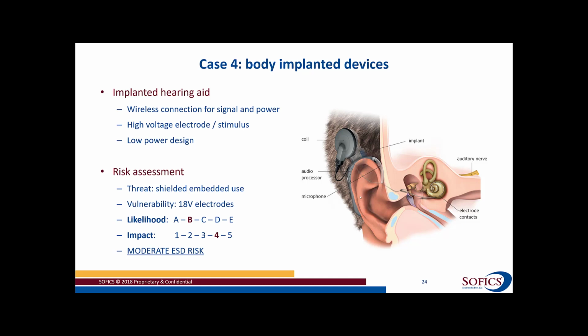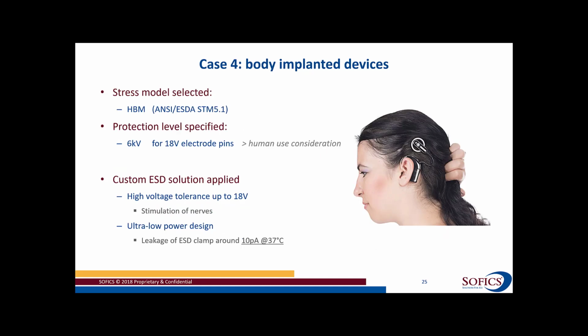What's the likelihood of something to happen? It's in the second column, B, and the impact is going to be higher, because if something happens, this is a body implanted device, so we cannot just ignore that. This leads to a moderate ESD risk. So what was selected in this particular case? Well, in the end, the human body model was used. However, it was an increased performance requirement of 6000 volts, not the standard 2000 volts or 1 kV, but 6 kV was applied.